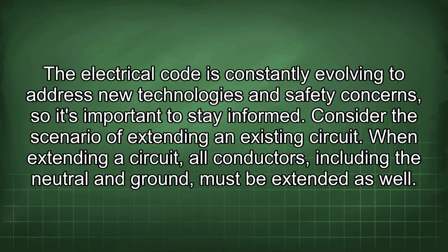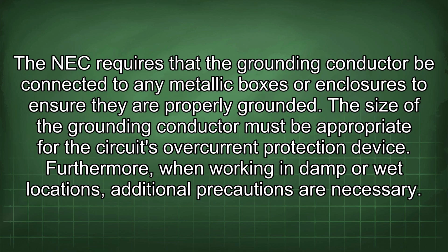Consider the scenario of extending an existing circuit. When extending a circuit, all conductors, including the neutral and ground, must be extended as well. The NEC requires that the grounding conductor be connected to any metallic boxes or enclosures to ensure they are properly grounded. The size of the grounding conductor must be appropriate for the circuit's overcurrent protection device.